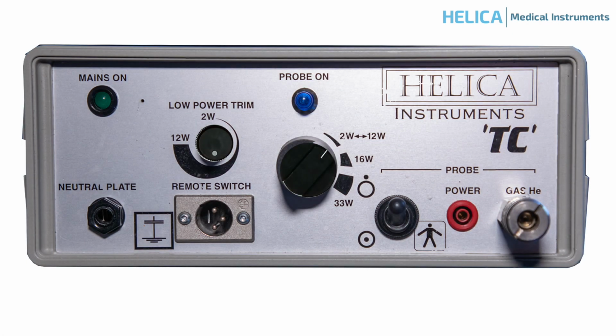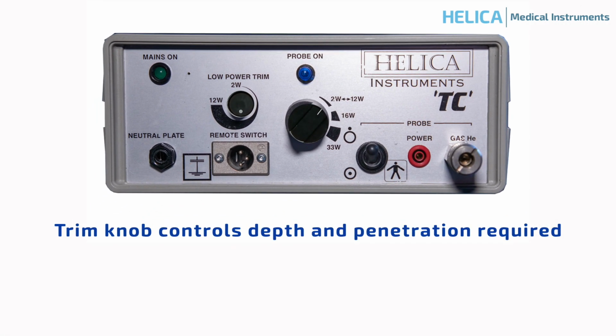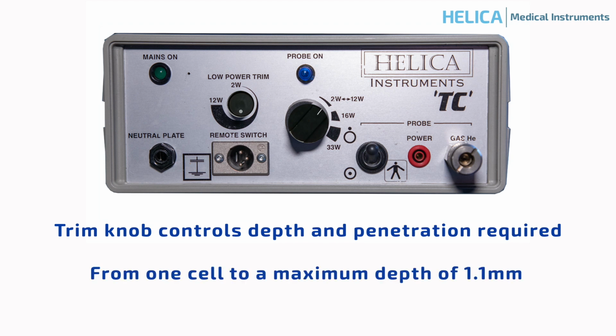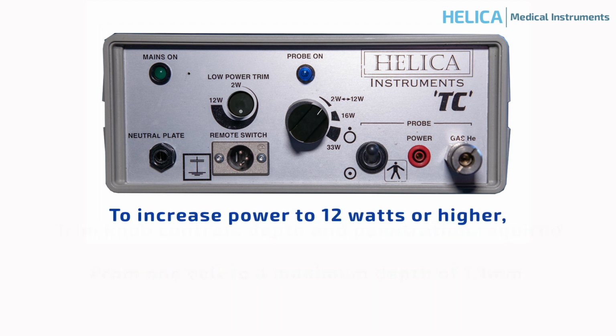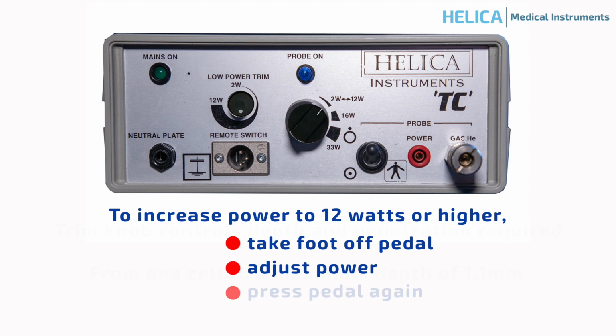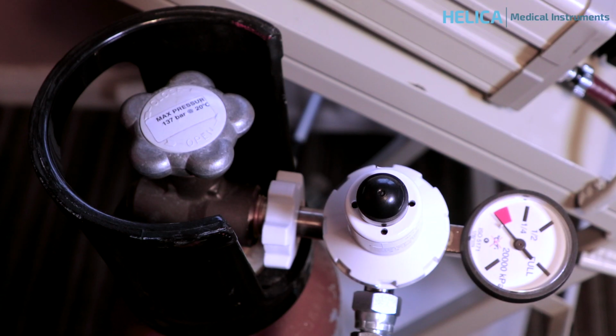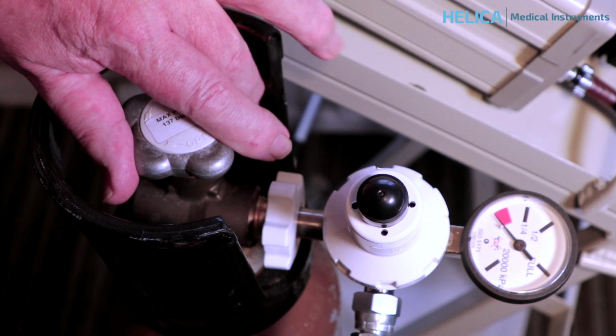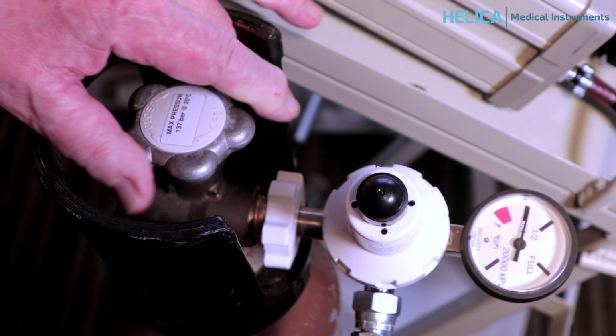The trim knob allows the surgeon to control the depth and penetration required, which, if necessary, could be as fine as 1 cell to a maximum depth of 1.1 mm. Further increase to 12 watts or higher can be made by taking your foot off the pedal, adjusting power, and then pressing the pedal again. There is no adjustment on the regulator on the gas bottle. Switch on the gas anti-clockwise.